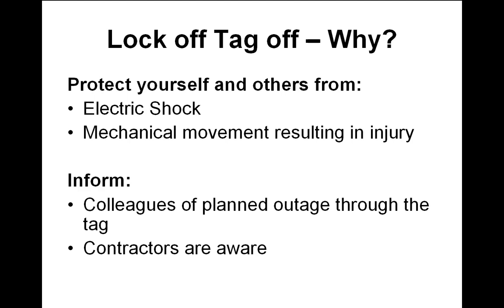The problem is that you work on a line, and somebody thinks, why is the line not working? Why is it being stopped? What's going on here? They might just go to the fuse box, and especially if it's just a trip fuse, they think, oh, it's tripped, and they just flick the trip switch, and the line is back working again whilst you're working on the equipment, and you might suffer an electric shock. So there has to be obviously a lock off, where you lock off the circuit protector, the circuit device, or the breaker, and then the other one is there should be ideally some information.